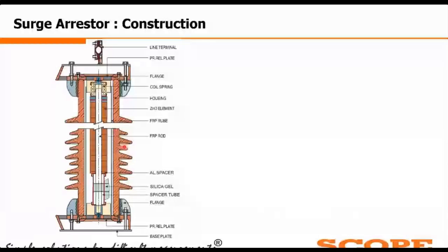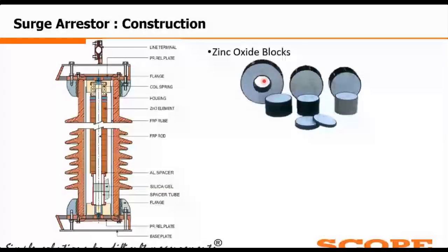Then inside that FRP tube, the ZnO blocks, zinc oxide blocks, will be available. Depending upon the construction, rating and design of the OEM, there could be an FRP rod at the center of the construction, or it may not be there. Like these are the ZnO blocks. If we use this type of ZnO block, then there will be an FRP tube at the center and another FRP tube at the outer surface, then outside that, the porcelain chamber. But for these sorts of blocks, there won't be any option of putting the FRP rod at the center.